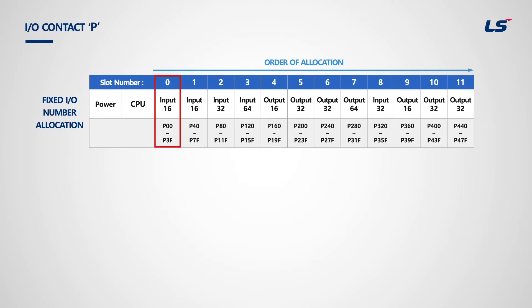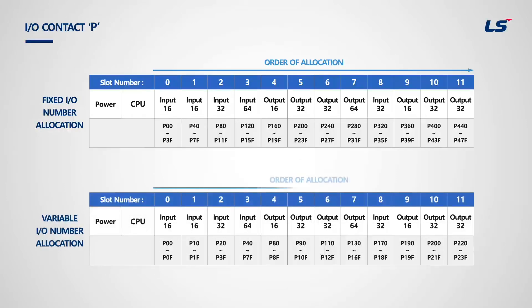For slot number 0 with fixed input-output number allocation, when an input-output module with 16 points is equipped, it will use P0 to PF. The remaining input-output devices from P10 to P3F can be used as internal memory. For variable input-output number allocation, input-output numbers are allocated based on actual modules equipped in PLC: one word for 16-point module, two words for 32-point, and four words for 64-point. If a user changes a module from 64 points to 32 points, the input-output numbers from that slot will be pushed back.